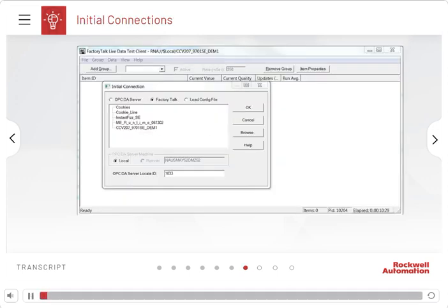To monitor the status of data items, or read or write their values, you must connect to the data server that is hosting the data items. Data server tags, also called direct reference tags, are referred to as data items within the FactoryTalk Live Data Test Client to match OPC-DA specification.